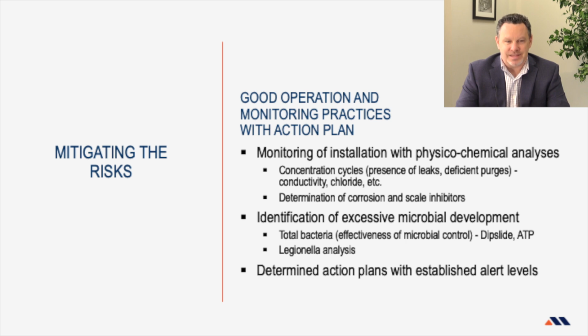Test, test, test. You need to test for bacteria. You can test for total bacteria count, but you can also test for Legionella specifically, which you cannot usually do at your site, but you can have an accredited lab do that for you. But you need to be testing. Without testing, you don't know what's happening. You can only guess. So that has to be part of your program in place.